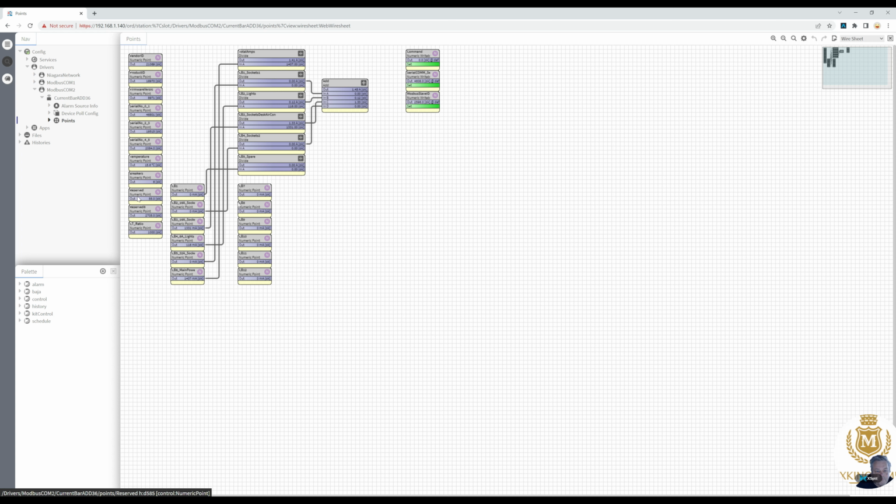So we've got the Modbus points coming in here via RS485. All I'm doing is putting these to a divide block and adding up the total amperage. And these three items here I can adjust if required. And this is just information: the vendor ID, product ID, firmware version, they're just read only, and we've got a temperature there of 16.4 degrees, and we're using 6 breakers.